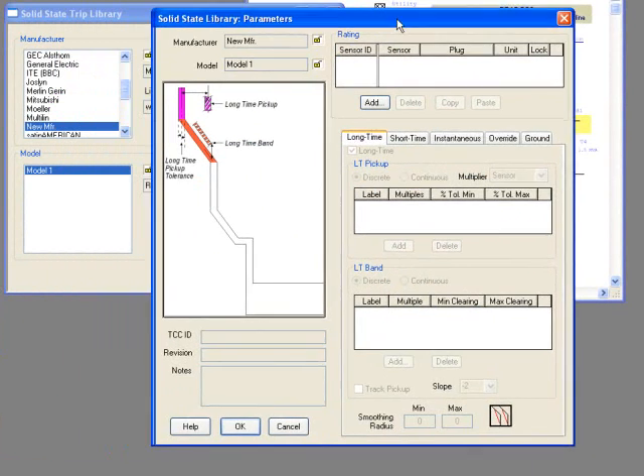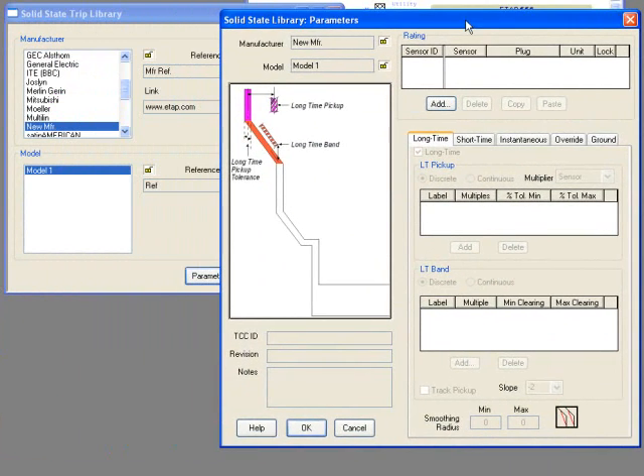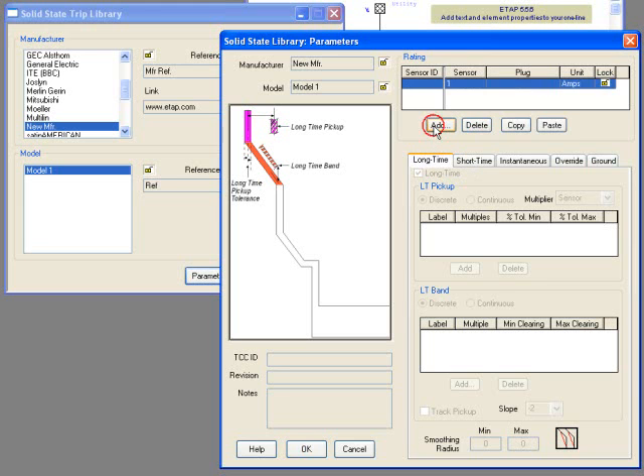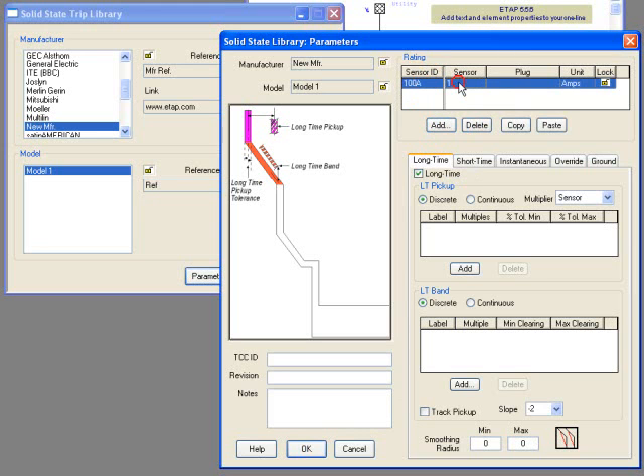As you can see, there are different tabs. To add new sensor, click on Add. Specify the sensor ID. Most likely, the sensor ID will equal the sensor amps. In this case, we'll enter 100 amps. For sensors that go with that plug, you can enter plug data. Keep in mind that you will have to use a colon to separate the different plugs.